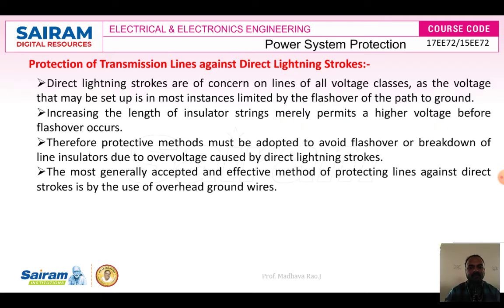Firstly, we will discuss protection of transmission lines against direct lightning strokes. Direct lightning strokes are a major concern in the power system, because due to them the entire transmission line can get damaged. Since transmission lines are placed outside, not inside, these are all outdoor installations, and we must consider direct lightning strokes for them. Direct lightning strokes are of concern on lines of all voltage classes, whether 66 kV, 33 kV, 11 kV, 132 kV, even 440 kV or 720 kV. All transmission lines we have to protect.